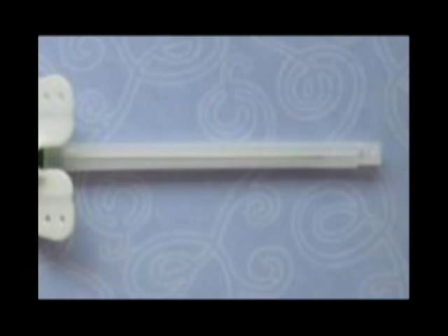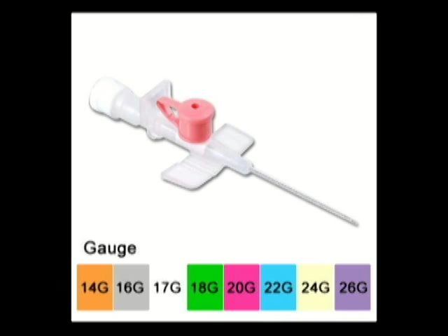The Health2000 IV cannula follows the standard color coding per gauge. Remember that the higher number gauge means the smaller in diameter. So for gauge 14, the standard color is orange, 16 is gray, 17 is white, 18 is green, 20 is pink, 22 is blue, 24 is yellow, and gauge 26 is violet.